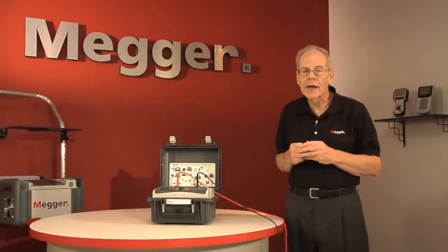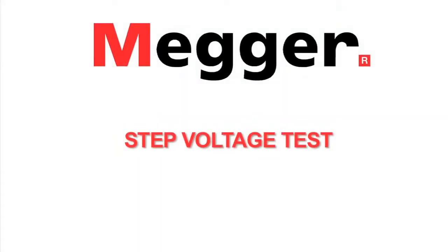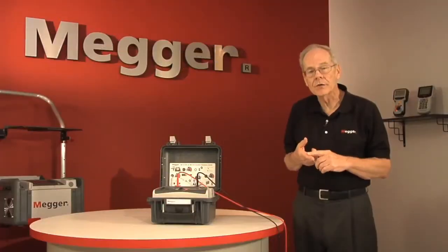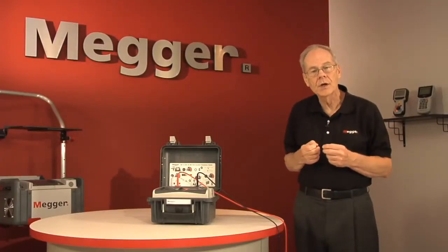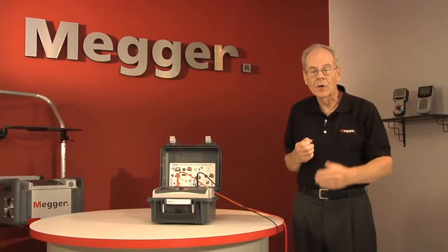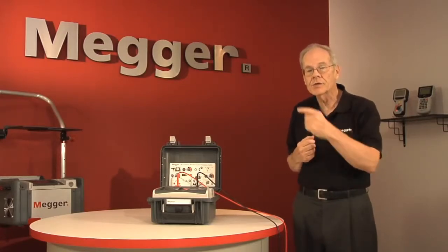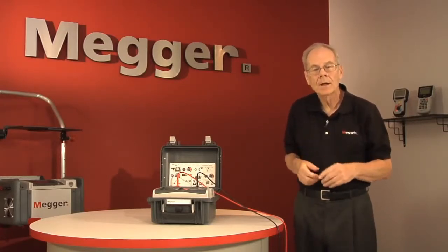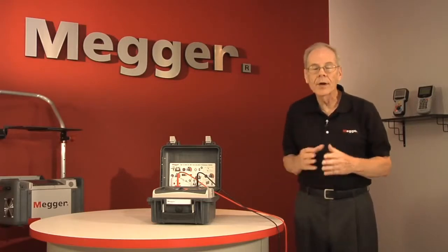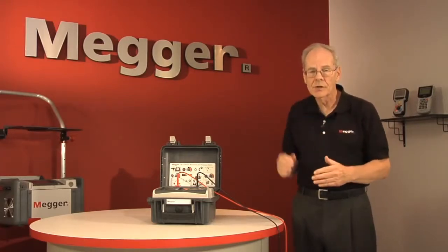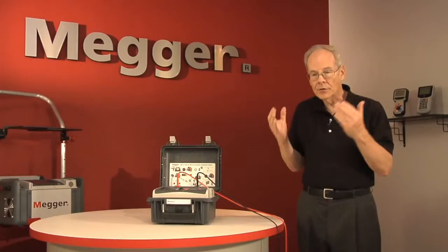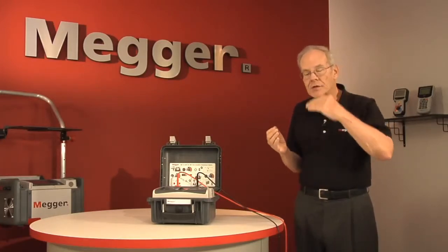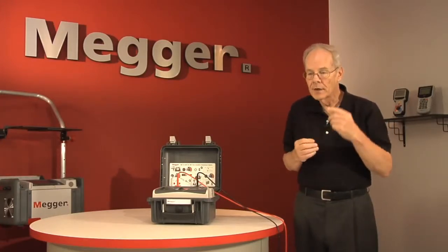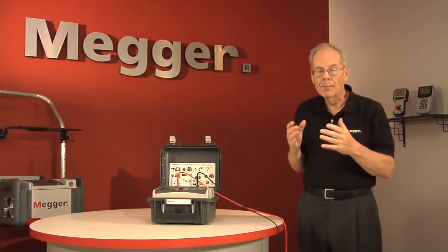The next test we'll look at is the step voltage test. Now, in this case, the tester applies a given voltage for a 1-minute interval and then automatically increases the voltage in steps. And in this case, the operator first selects the voltage ceiling that you want to test to, in which case it will divide that into 5 equal increments for 1 minute each.